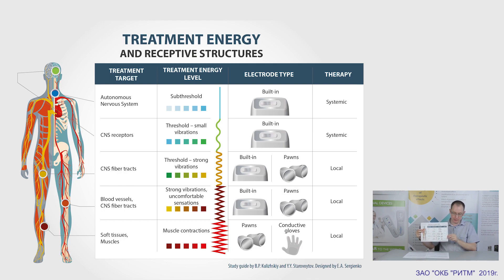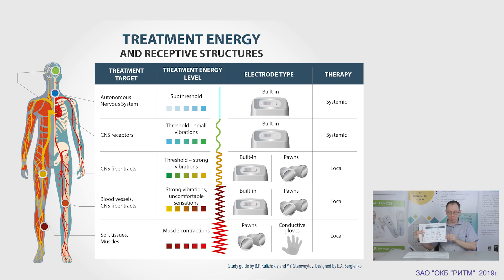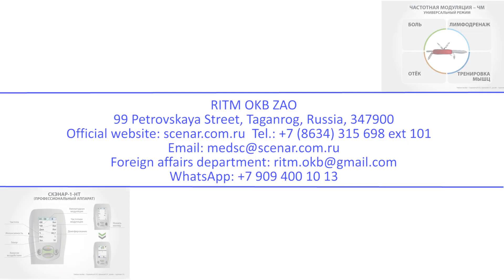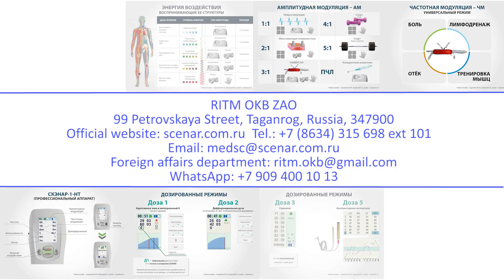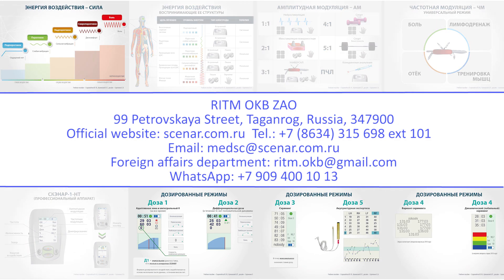This level is used for myostimulation and treatment of the locomotor system. The main electrodes to use here are pawns and conductive gloves. Energy higher than the supra-threshold is used only for competitive analgesia — for example, when we use the bee sting mode.